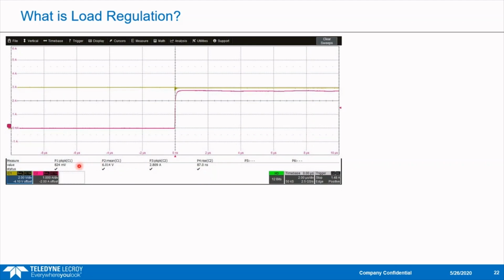On channel 1, I've got a peak-to-peak deviation of 8.24 millivolts. The power supply didn't know there was going to be a large load change, so of course it's not prepared for it, and there's going to be some deviation. So I've got the deviation, and I could also measure the specification, which is the before voltage and the after voltage, and compare those against the specification.